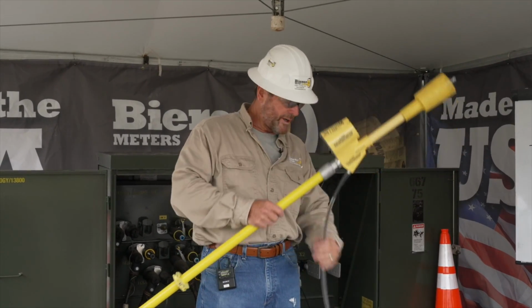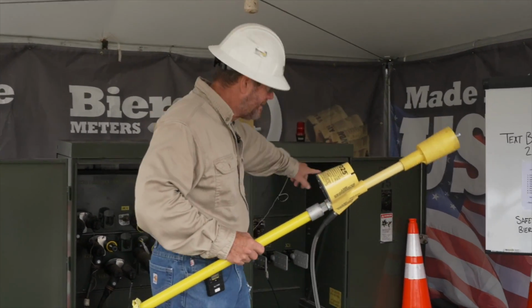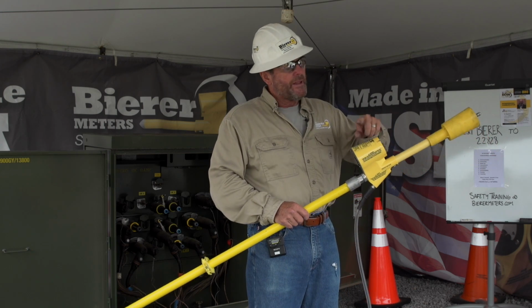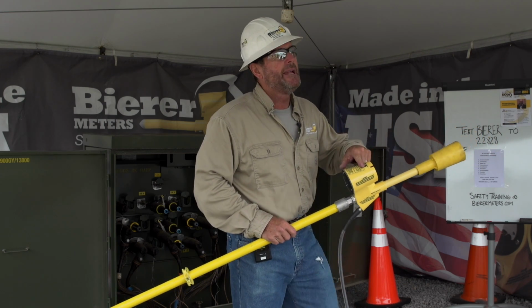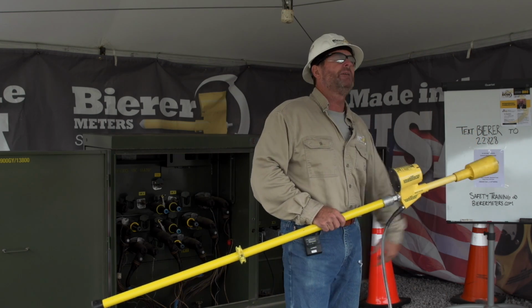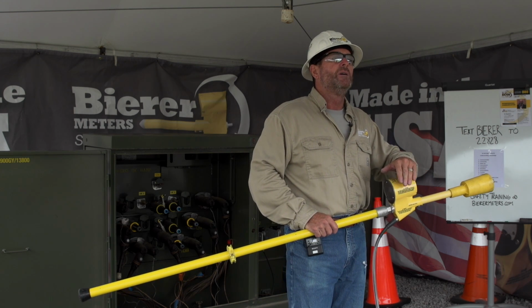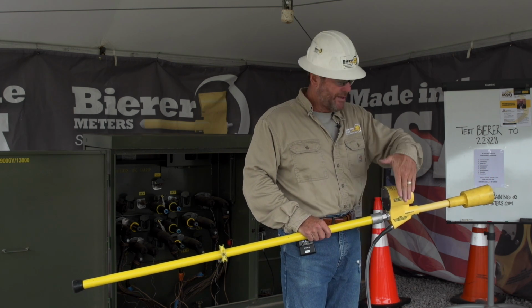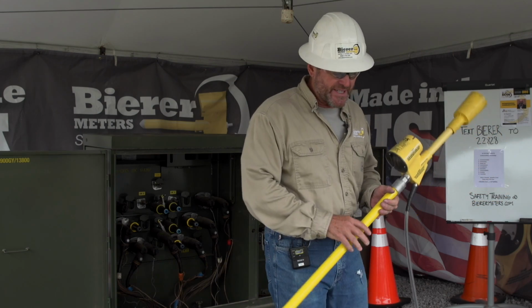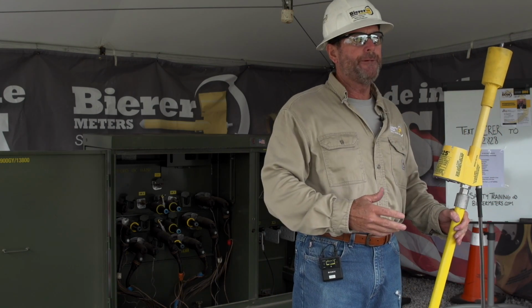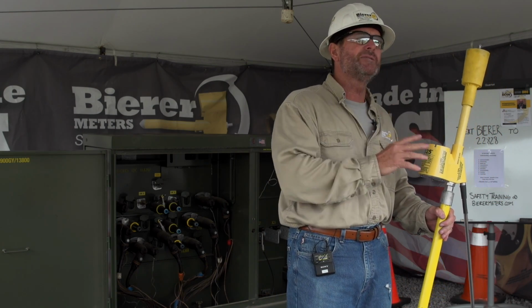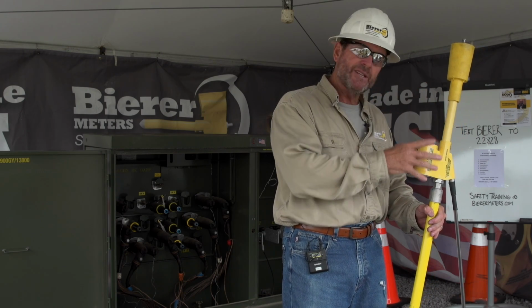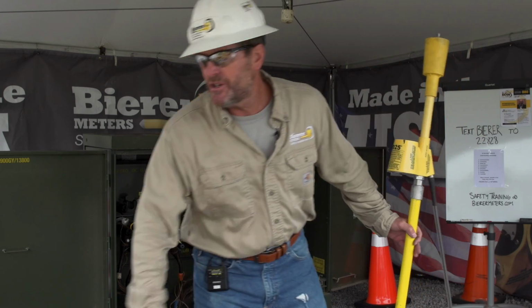Check this out, corded, phase to ground, going to ground. In this particular utility, the meter head was next to another hot phase. So instead of inspecting their work area prior to using the tool and knowing how these tools function, they should have put on a zero ohm extension.